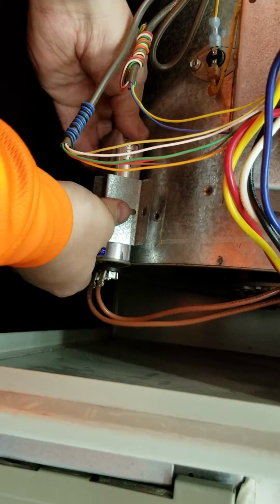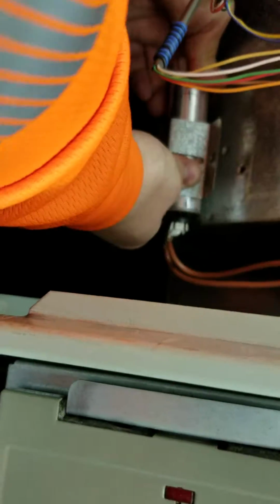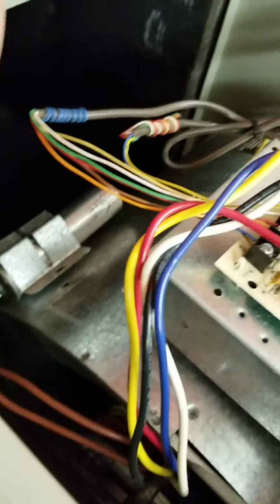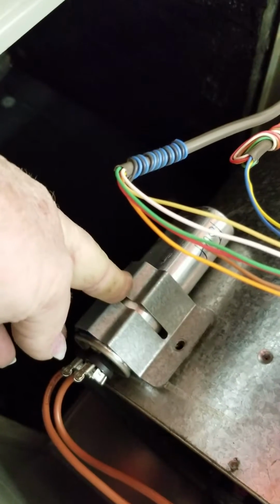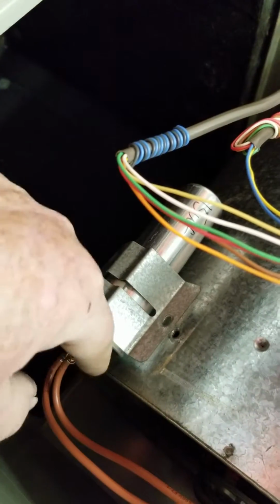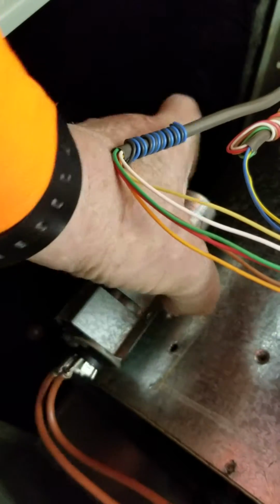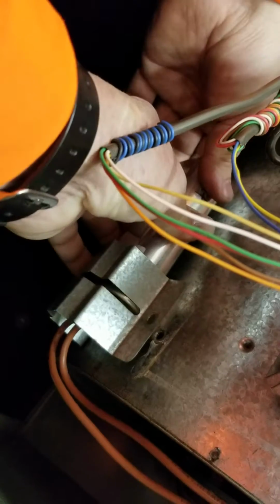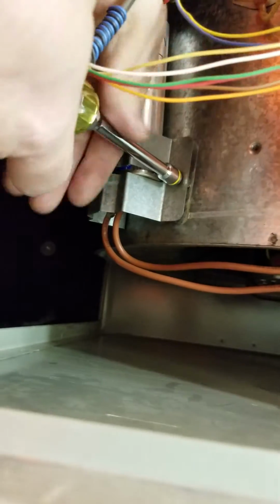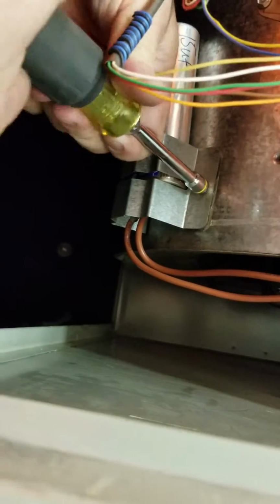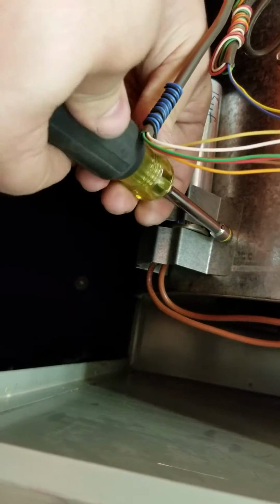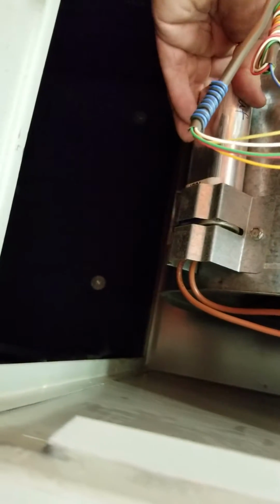Reinstall it in the bracket and make sure you've got the bracket secured. Again, also watch your ends when you put this up so that it doesn't short this out. This should actually go there. That way the wires are not shorted out against the edge, that lip of the cabinet, the blower housing. And they are shielded from contact with other parts of the furnace.